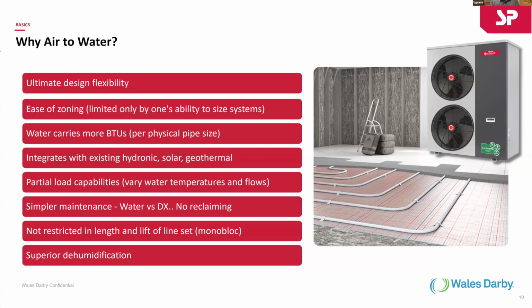Now, you've got a modern kitchen put in. You put in tile, a modern bathroom. There's a tile floor. You want to put radiant in that floor. Well, guess what? You can do that. You can put the radiant in there and have your cast iron radiators. And now upstairs, you've got some baseboard. Well, we'll put in baseboard. So it just lends a lot of flexibility in what we can do. And especially for what you guys are doing, no one project is the same, right? They're all different. They all have their own characteristics. So this will lend itself to doing that. The domestic hot water can also be made with it. So there are a lot of good pluses that go with using this air to water.